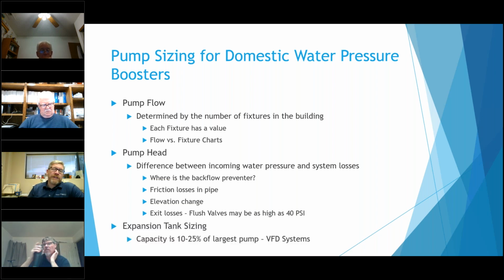The other thing you want to have is an expansion tank on these. They add just a little buffer tank. It's probably been 10 years since I've sold a constant speed pressure booster, so I think most people use a VFD driven one. So this is 10 to 25% capacity of the largest pump. That's where the pump would actually go out on the curve. Your pump might be designed to handle 50 GPM, or that's what your system would require, but the pump can go out to like 75.